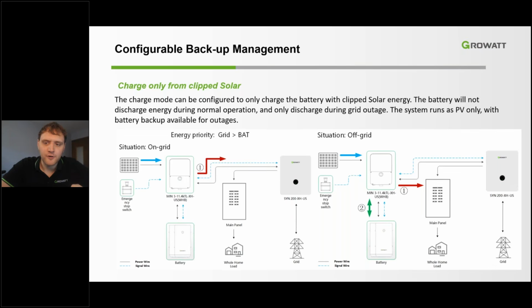This mode allows the inverter to operate on-grid as if there were essentially no battery, allowing the customer to sell back more energy to the utility and power the customer load in the most optimal way. If the solar energy is not sufficient, the grid will power the customer load, and in the event of blackout, the backup mode will run as normal and charge the battery from the generator and clipped solar production.